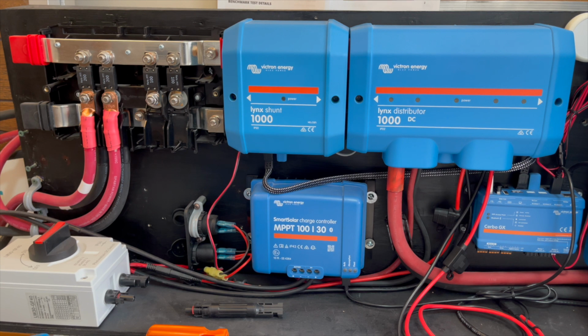If you see an improvement and it's still bad, then I would probably take the server racks and check to see if there are loose connections inside the server rack, especially the one that probably has way off readings compared to the others. Now, not all BMS are smart BMS. I noticed some use their own in-house, or some unknown brand. Who knows how long it's been out, how well it's been tested. Maybe there's firmware above it. So those are possibilities.